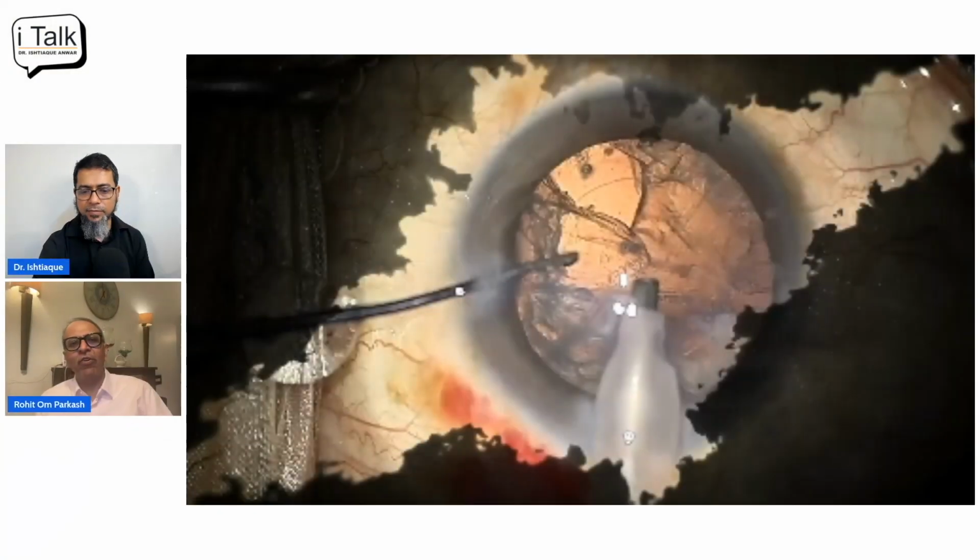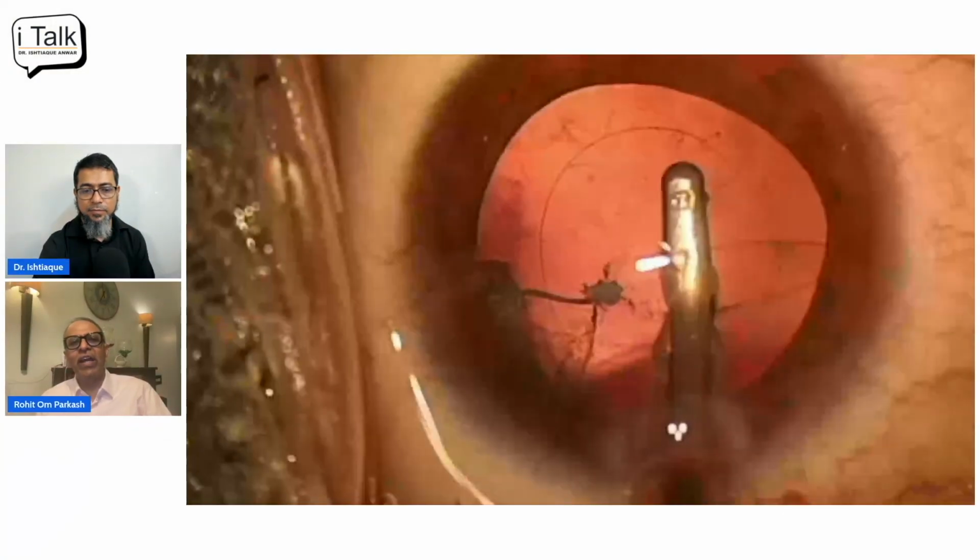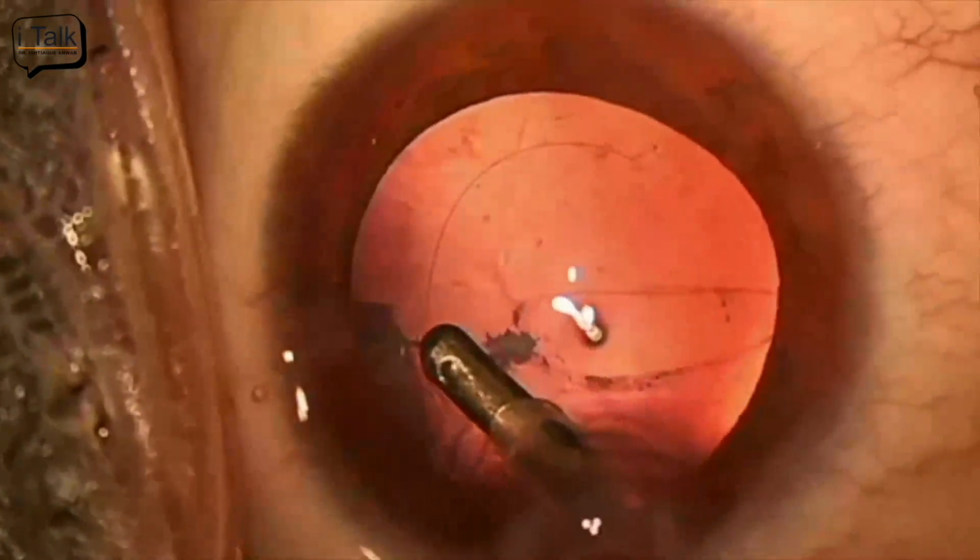It's always better to do surgery at low parameters. But there are surgeons who prefer to do surgery at high parameters. If there is any complication, we should lower all the parameters as soon as possible.